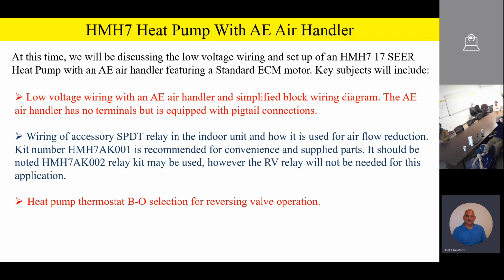Now, this is going to be important because as we set up this heat pump with an indoor product, we want to be able to reduce our airflow to 60% airflow when we have that low airflow command. And then high airflow, of course, will be 100% airflow based on 400 CFM per ton of cooling capacity. So let's go ahead and talk through that for a minute or two.